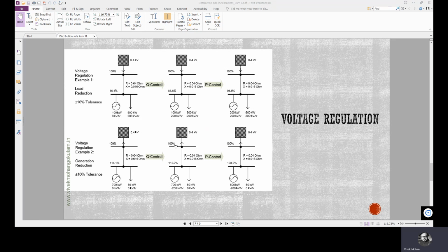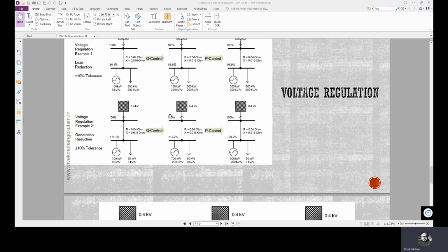So this is another example of providing voltage regulation service by means of reactive power control and active power control from the micro sources. Now in the second example, we have 700 kilowatts of local generation but 50 kilowatts of load. So there is excess generation and 650 is pumped. Actually, when it reaches here, the loss must be deducted. But anyway, if loss is assumed to be 0, then 650 is reaching here, right, to the upstream grid.